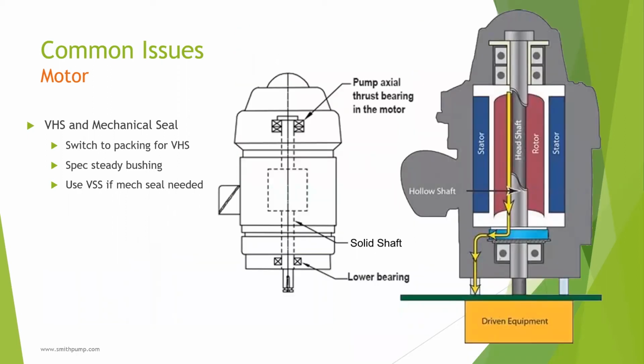A vertical solid shaft motor begins with less runout because it has a lower bearing close to the seal, shown right there. The pump shaft in a hollow shaft motor runs in a tube. So this tube is the rotor shaft. It has supporting bearings on top and bottom. However, the pump shaft does not have a lower bearing to restrict shaft movement. Therefore, the shaft has a potential for higher runout values. In summary, use a solid shaft motor if using a mechanical seal.